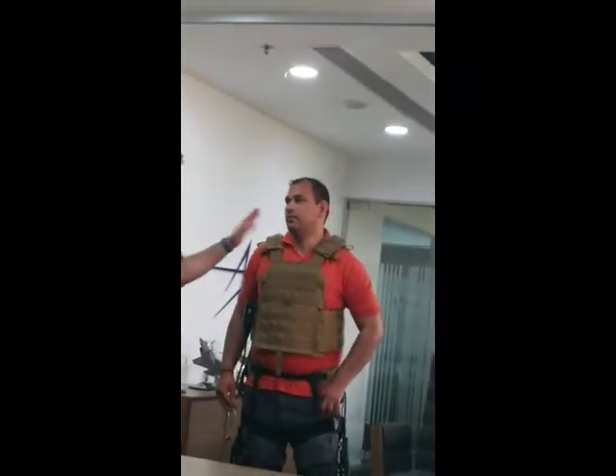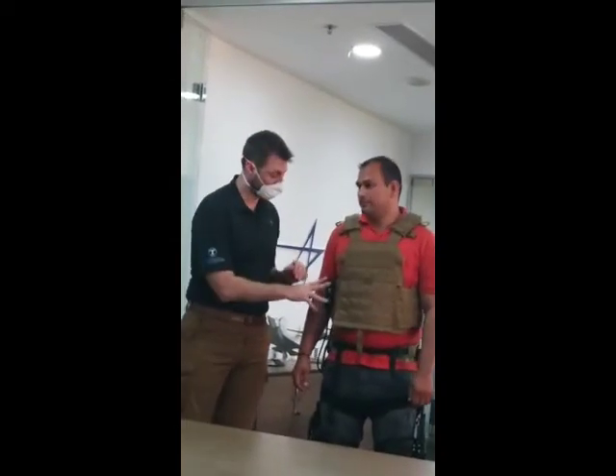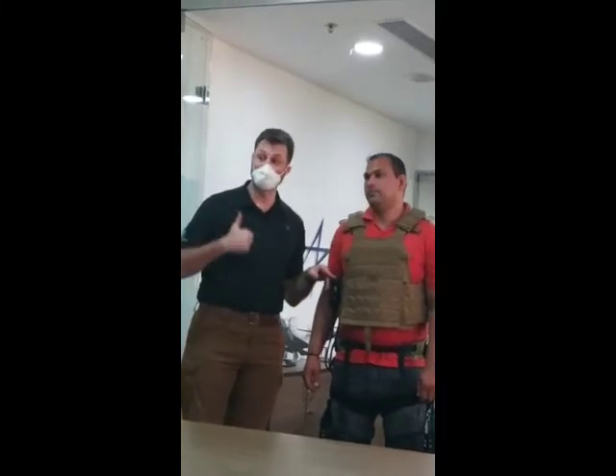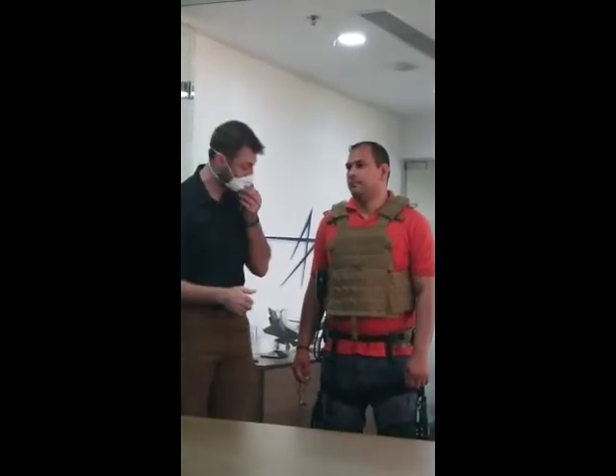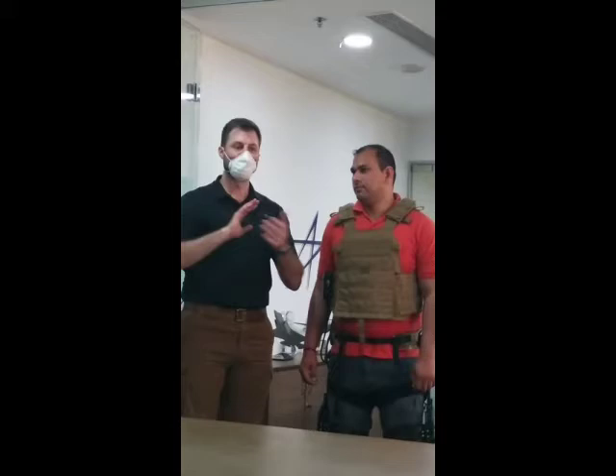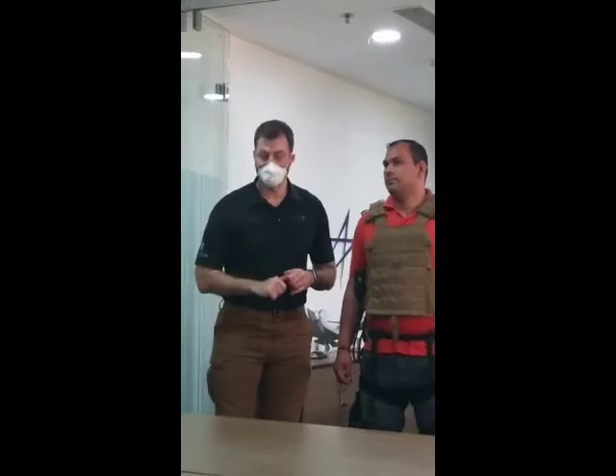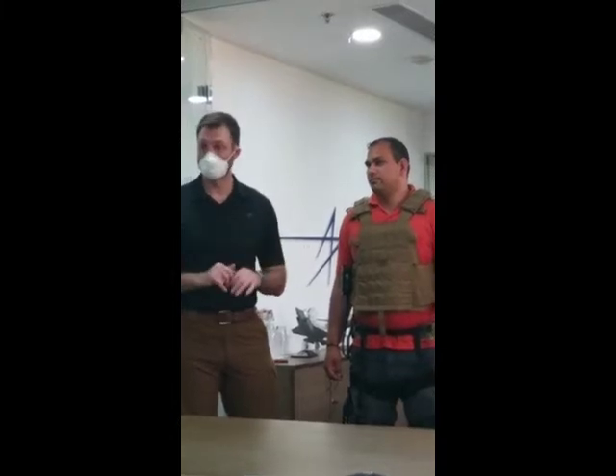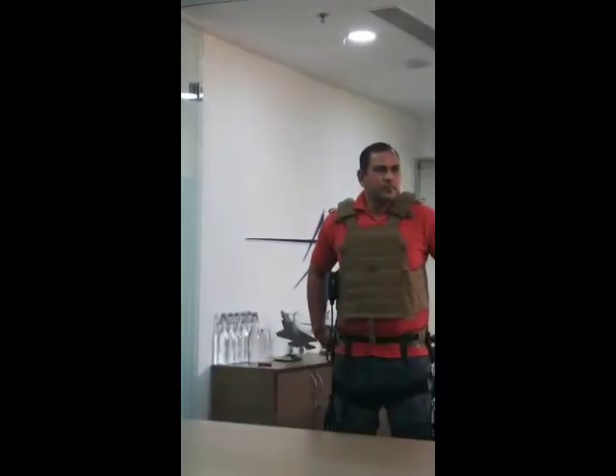So now the suit is powered, and it's in a standby state. The control module has three buttons here. The first one takes it from standby to activated. The second is a power intensity, which scales the amount of assistance he receives. And the last one is a switch that lets you have potential other modes of operation or presets. For most operations, we only care about the power on-off and the power intensity, which once again speaks to the transparency aspect of it. Once the user knows, I want this amount of power, they can set it and leave it from there, and they just use the exoskeleton. There's no need to deal with a whole host of functions because it's just there to provide him that assistance.